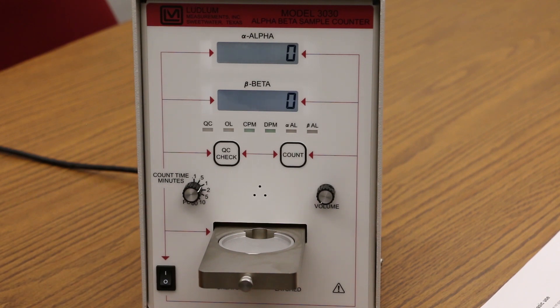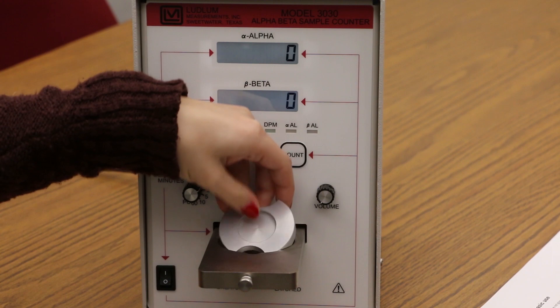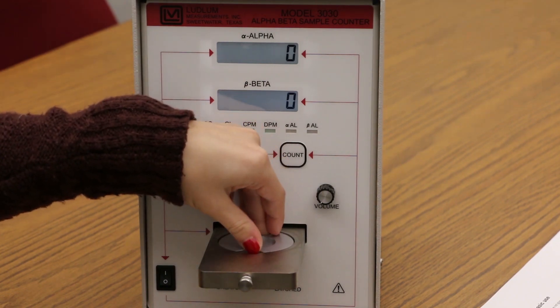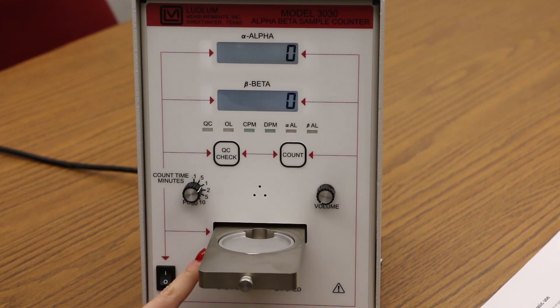A sample drawer that is used to hold the sample during a count cycle. Inside the sample drawer is a reversible tray insert. The insert can hold samples up to either two and a half centimeters or five centimeters in diameter and is one centimeter thick. The tray insert is held in place by a set screw on the left side.